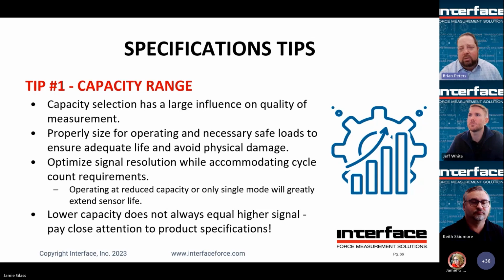Especially keep in mind too, if it's single mode. Our fatigue rated load cells, as you heard from Jeff, are rated for 100 million fully reversed cycles, right? That's both directions. When you're not doing cyclic loading, that also greatly reduces the chance of any fatigue risk. So if you're doing just compression only or just tension only cycle, you're likely going to be fine with a non-fatigue rated one, especially if you're only operating at, say, 30–50% of that load cell's capacity. So these are good discussions to have with the AEs, the application engineers, to figure out exactly how much capacity you need.